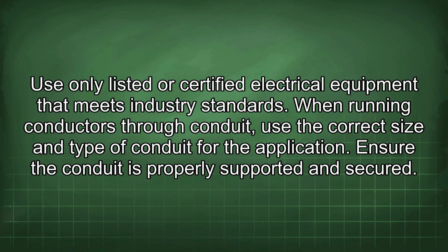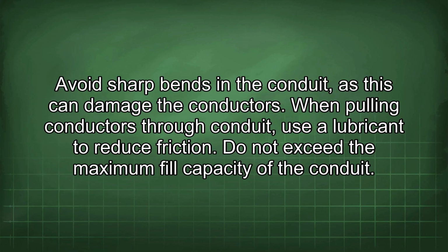When running conductors through conduit, use the correct size and type of conduit for the application. Ensure the conduit is properly supported and secured. Avoid sharp bends in the conduit, as this can damage the conductors. When pulling conductors through conduit, use a lubricant to reduce friction. Do not exceed the maximum fill capacity of the conduit.